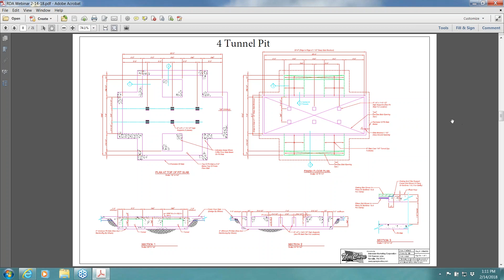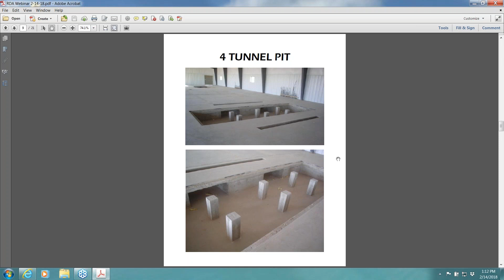Now this 4-tunnel pit, here's an actual picture of it in a finished floor. The way we do this particular model is it's built on a side exhaust style cabin with boxes down each side, sitting over this 4-tunnel pit, and the air moves through these side openings, through the pit, and up through the side openings. You'll see something like this in different styles and configurations, but you can tell these pillars are formed out of concrete, and you can see the tunnels, how they're formed underneath, going to these openings. So all of that construction goes into getting those pits into the ground.